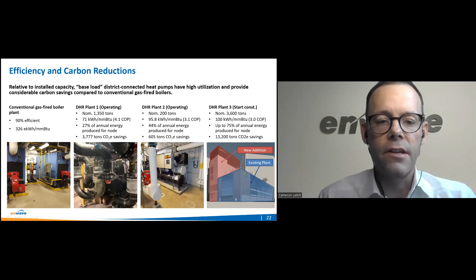Through the design, construction, and operation of DHR Plants 1 and 2, there were lessons learned that informed our approach for DHR Plant 3. As it relates to the heat pump selection, our primary focus was to maximize utilization. Traditionally, heat pumps have been able to produce temperatures that are slightly above those in a typical cooling tower loop. By increasing this temperature, we can serve year-round domestic water heating loads and encourage uptake by existing buildings that may have legacy systems with higher temperature requirements.